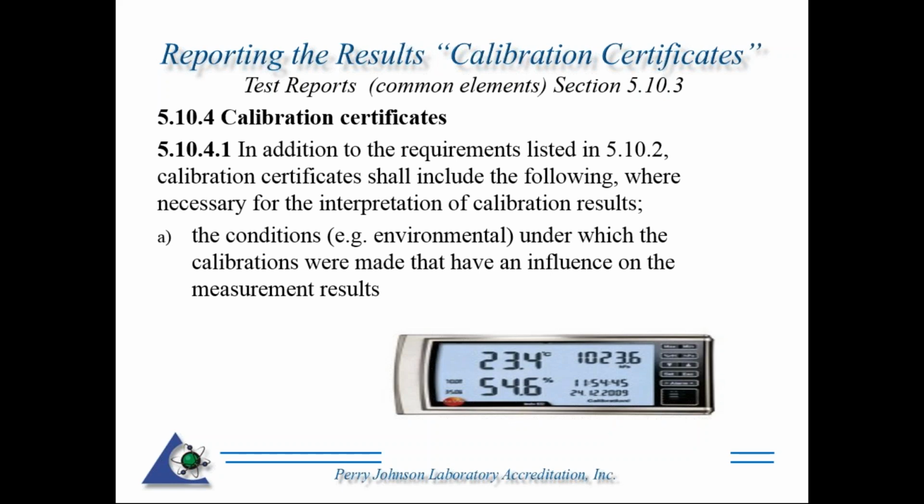Okay, we now shift gears here. We did testing. Section 5.10 looked at testing and sampling. Now we're in 5.10.4, which is specific to calibration certificates. So in addition to the requirements listed in 5.10.2, which are common requirements, calibration certificates shall include the following where necessary for the interpretation of calibration results.